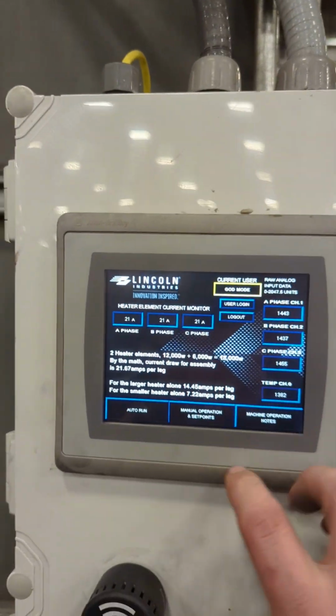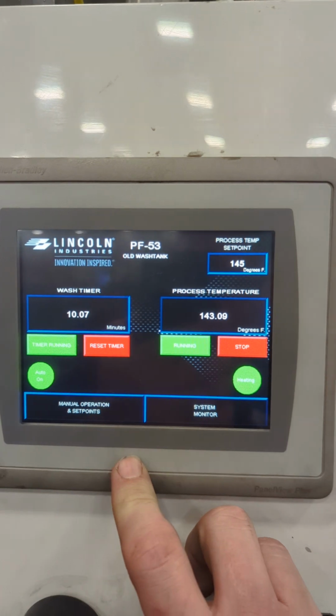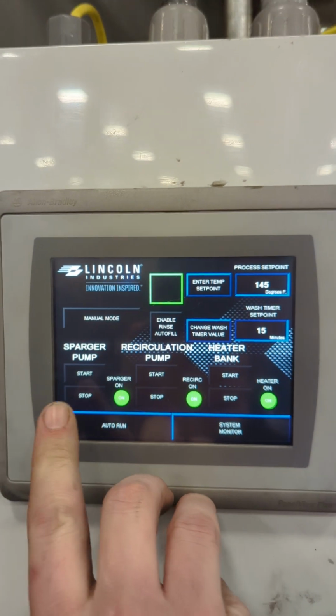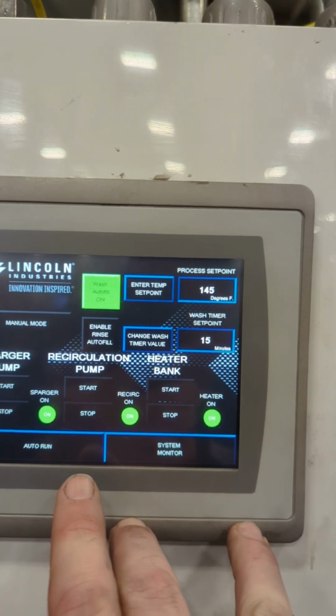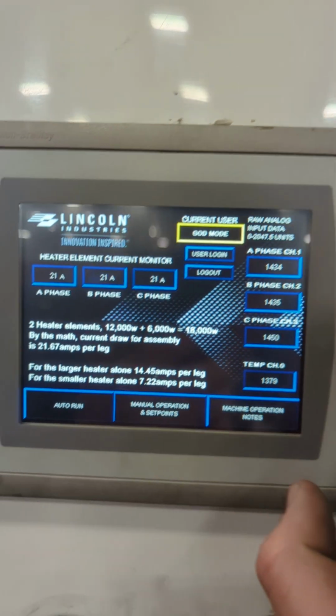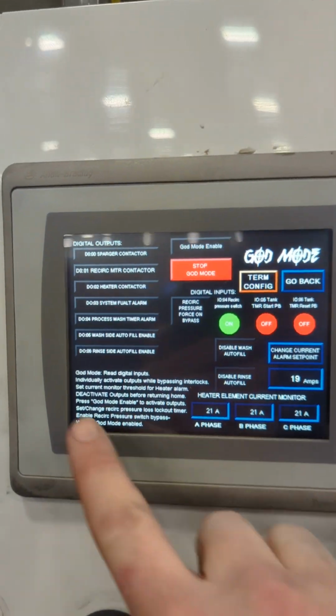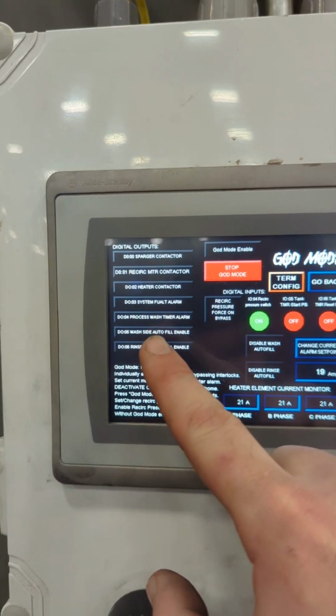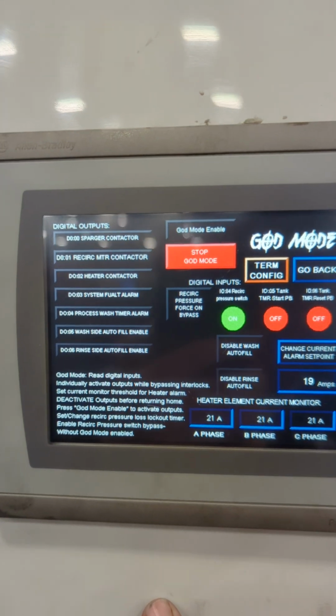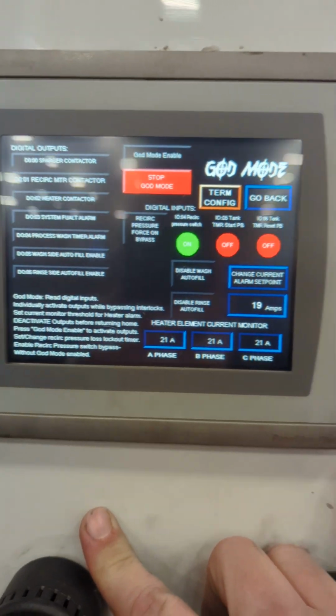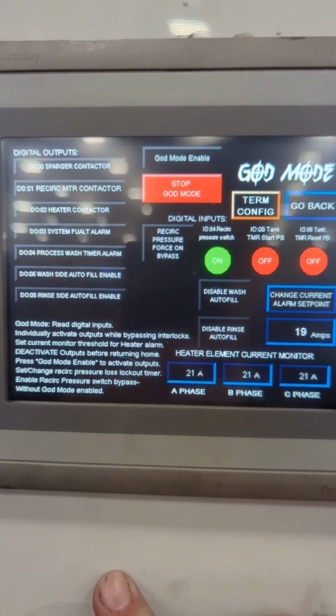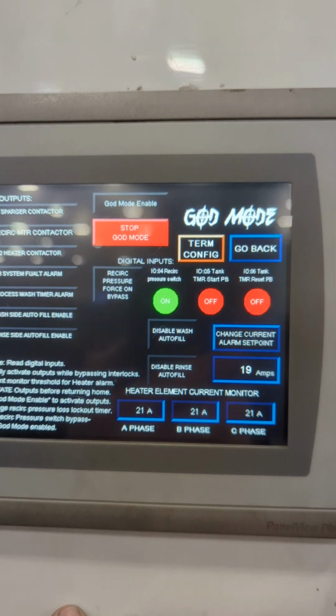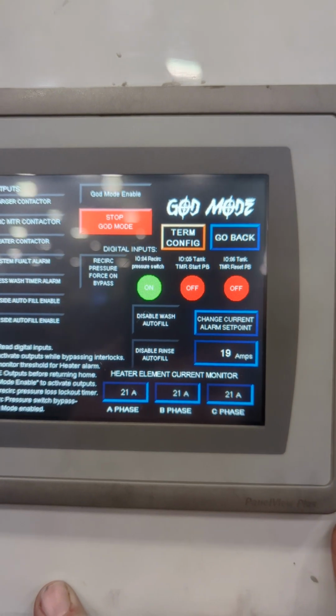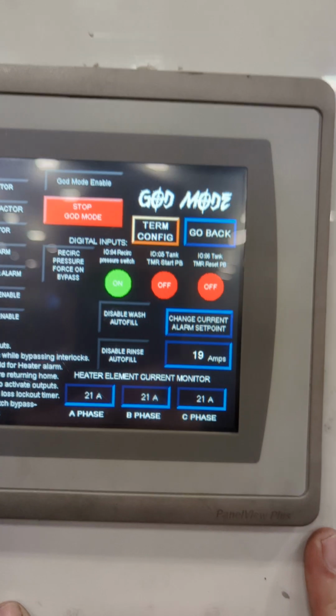Let's see. I got my auto run page, manual run page. Everything's black themed. If it's not on, it's not engaged, it's black. I got a God mode. I've already logged in. God mode will let me come in, and for troubleshooting purposes, I can enable each and every output regardless of any interlocks, and that allows me to troubleshoot anything that's going on from the console without hooking up the PLC. I could modify basically everything except for 2 things in the program from the HMI, so that's really nice.